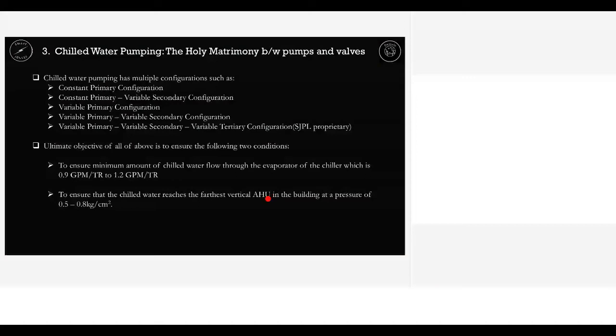So at all times of the day, you need not maintain a constant flow, because in a hospital building itself, the outpatient departments, many OPs, or maybe some labs, reception areas, canteen areas, they all don't function for 24 hours. They only function for 10 hours, 12 hours, 8 hours, something like that. And even in operation theaters, they operate on demand.